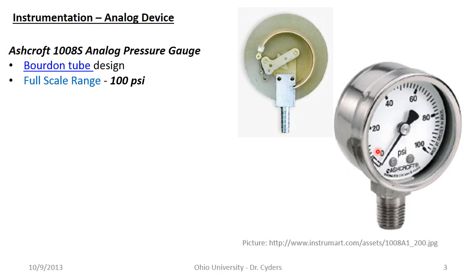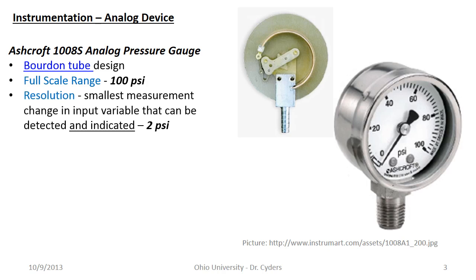This gauge has a full-scale range of 0 to 100 psi, meaning the full-scale range is 100 psi — the difference between the two numbers, not the absolute value. The resolution is the smallest change in the input variable — in this case pressure — that can be detected and indicated. Looking at the gauge, the smallest graduations are 2 psi apart, so 2 psi is the smallest resolution. We can't really register much of a change beyond what we can read on the face of the device.